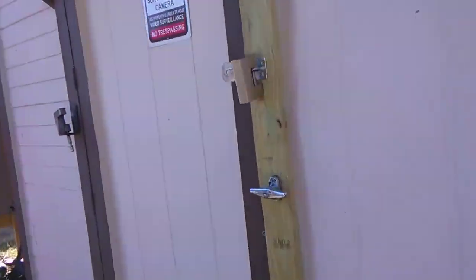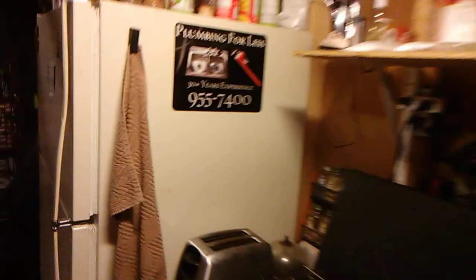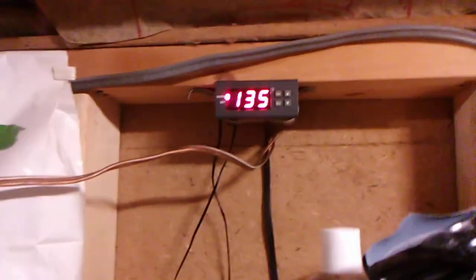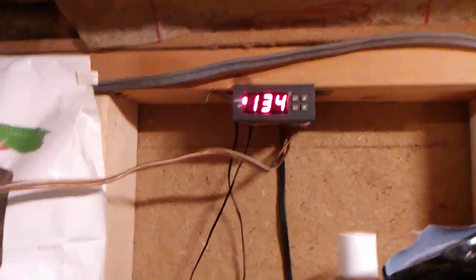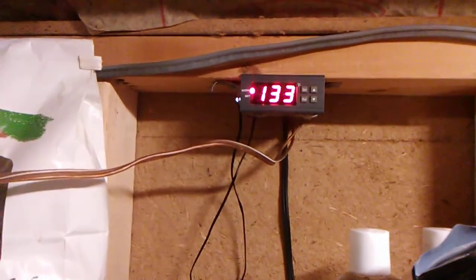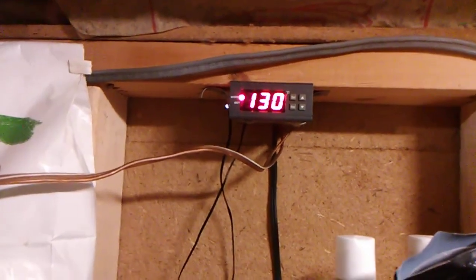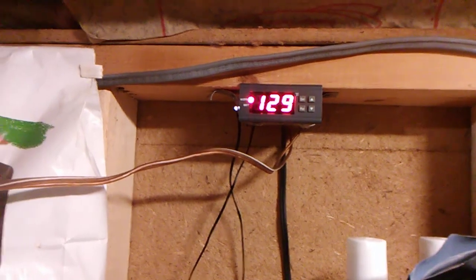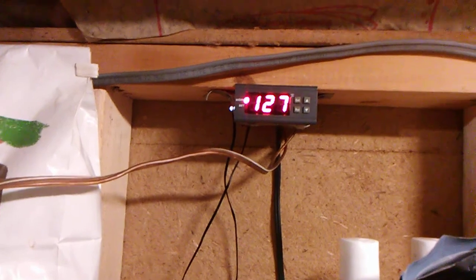Inside the shed, here's where it comes in, and that's the thermostat that senses the temperature in the box. There's a 20-degree spread — it cuts off at 135 degrees and turns back on at 115. It just came back on, so the temperature is dropping, and when it gets down to 115 it'll stop and wait for it to heat back up again.